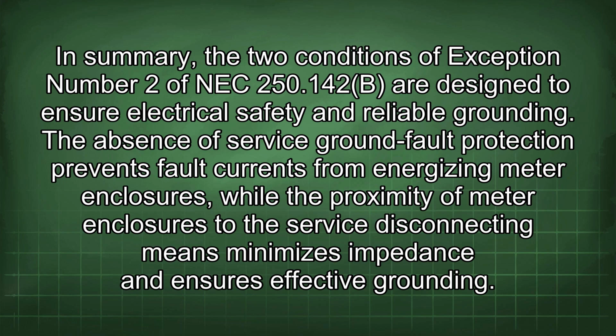In summary, the two conditions of exception number 2 of NEC 250.142(b) are designed to ensure electrical safety and reliable grounding. The absence of service ground fault protection prevents fault currents from energizing meter enclosures, while the proximity of meter enclosures to the service disconnecting means minimizes impedance and ensures effective grounding.